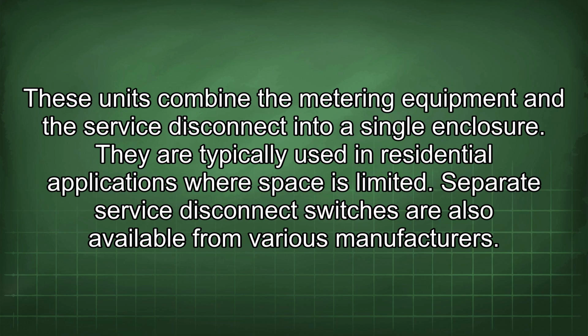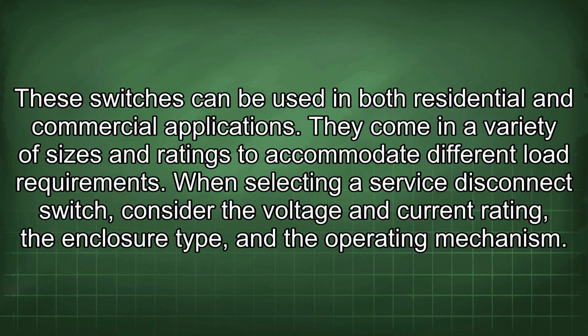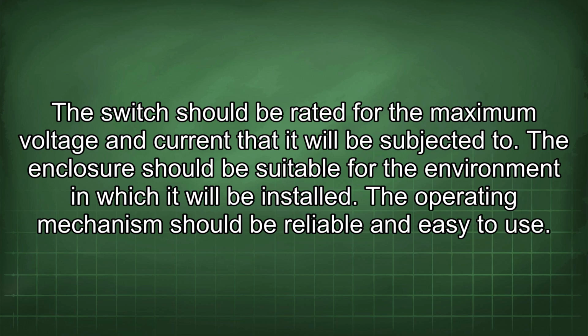Separate service disconnect switches are also available from various manufacturers. These switches can be used in both residential and commercial applications. They come in a variety of sizes and ratings to accommodate different load requirements. When selecting a service disconnect switch, consider the voltage and current rating, the enclosure type, and the operating mechanism. The switch should be rated for the maximum voltage and current that it will be subjected to.